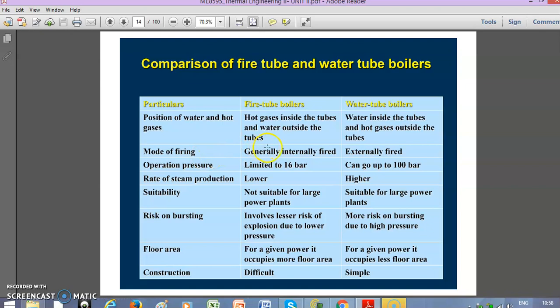The mode of firing: it is generally internally fired for fire tube boilers and externally fired for water tube boilers. The operation pressure is normally limited to 16 bar for fire tube boilers, so these are preferred only for low pressure cases.